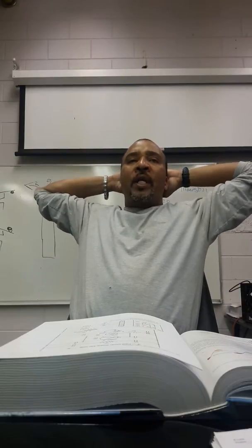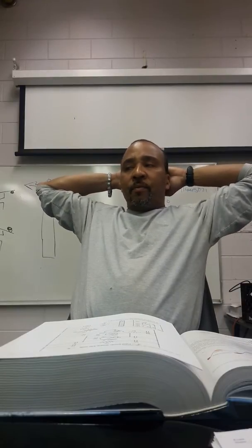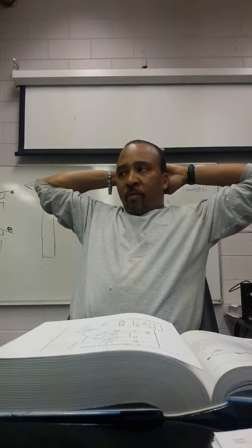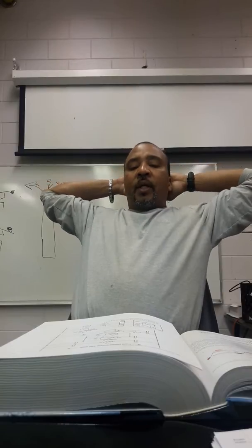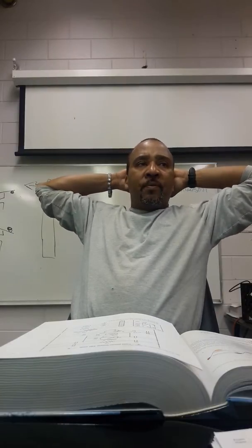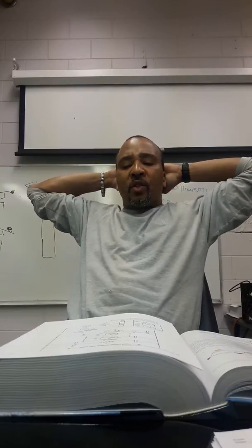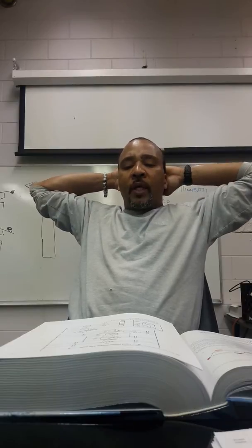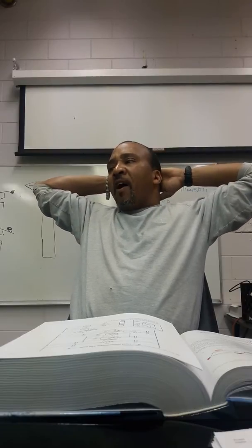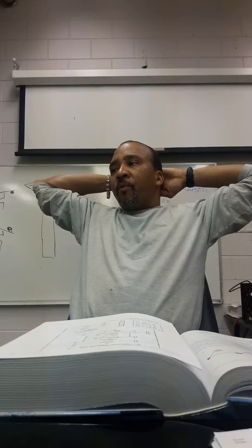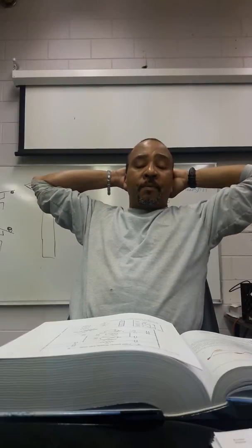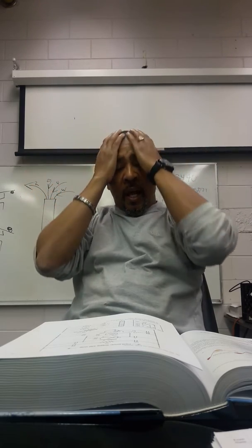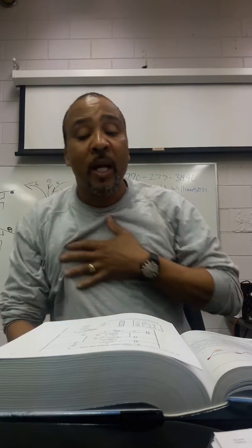Now, by doing that, what did I do by clipping from R to G? You bypass the selected switch. If everything is correct past that, the fan will come on. That's correct. If I jump it from R to G, I am going to bypass the thermostat. And if the thermostat is bad or not working, I am going to energize the IFR and the fan should come on. But if the fan does not come on, thermostat is not my problem.